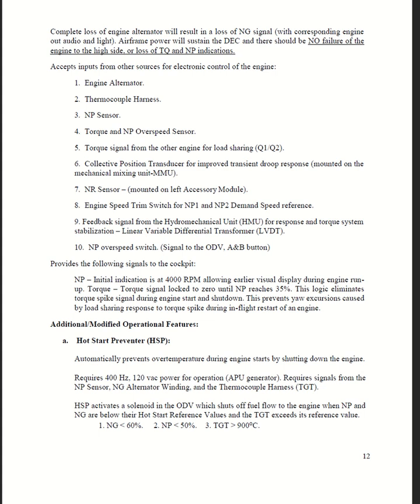That's the engine alternator, thermocouple harness, NP sensor, torque and NP overspeed sensor, torque signal from the other engine for load sharing for torque 1 and torque 2, collective position transducer for improved transient droop response, which is mounted on the mechanical mixing unit, NR sensor, which is mounted on the left accessory module, the engine speed trim switch for NP1 and NP2 demand speed reference, feedback signal from the hydromechanical unit for response and torque system stabilization. Linear variable differential transformer, LVDT, is also provided. NP overspeed switch signals to the ODV and the A and B button.